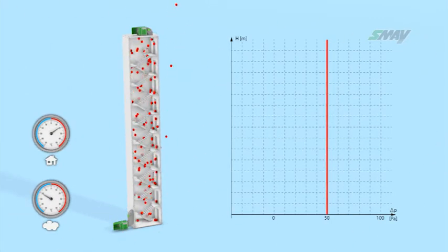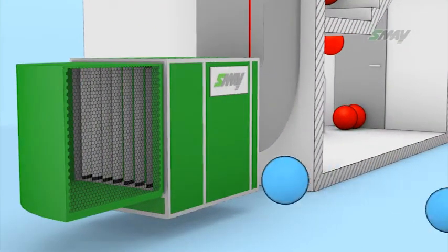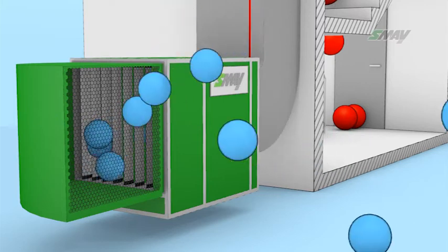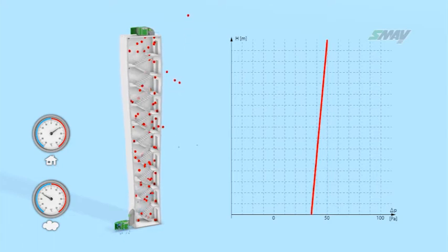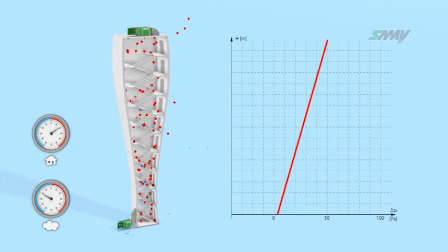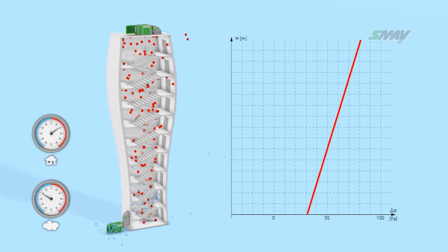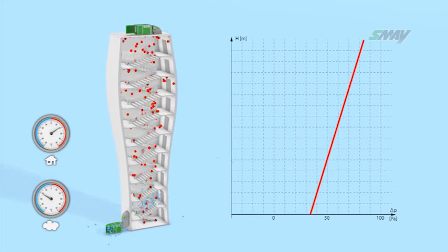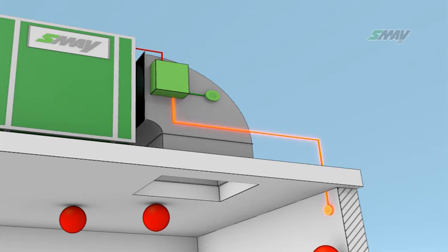If the external air temperature is below the temperature inside the stairwell, the system works in the same direction as in the event of no temperature difference — the bottom fan supplies air and the top fan works as an extractor, activating when 50 pascal are exceeded. Supplying the stairwell with external air, the stack effect will occur within its volume, causing temporary negative pressure in the lower sections. The pressure drop causes the bottom fan to supply more and more air, aiming to maintain 50 pascal in the lower section and causing a pressure increase in the entire stairwell. The excessive pressure increase in the upper part acts as the signal opening the dampers by the upper fan, which removes the excess air.